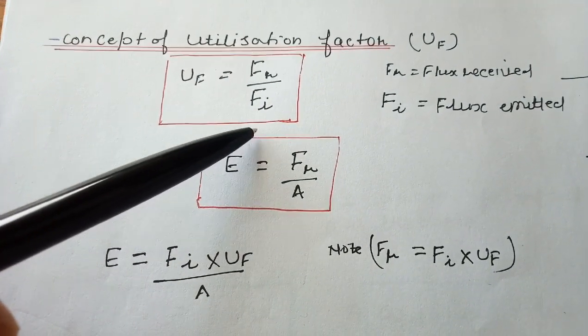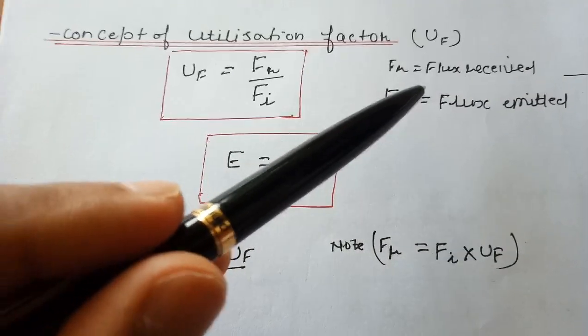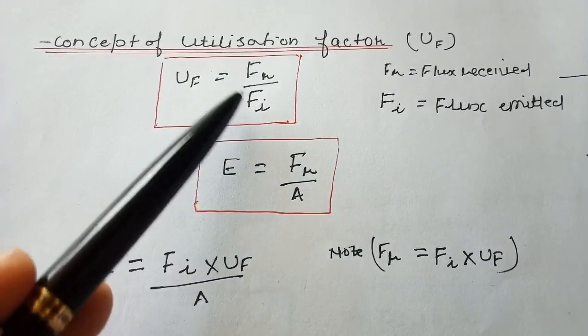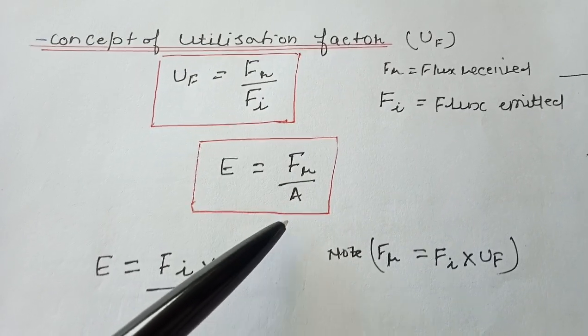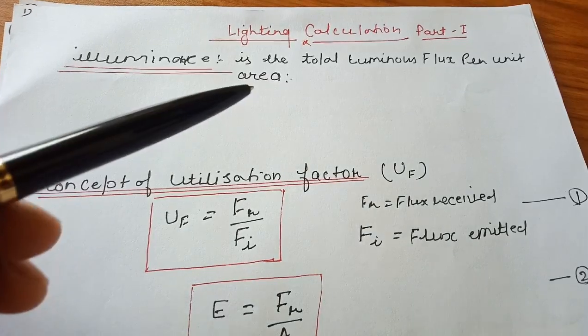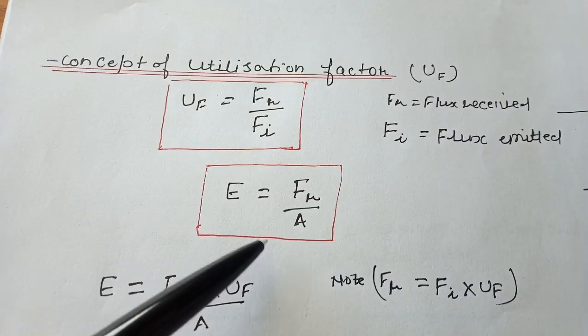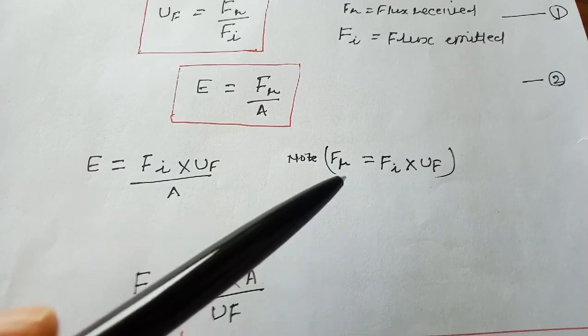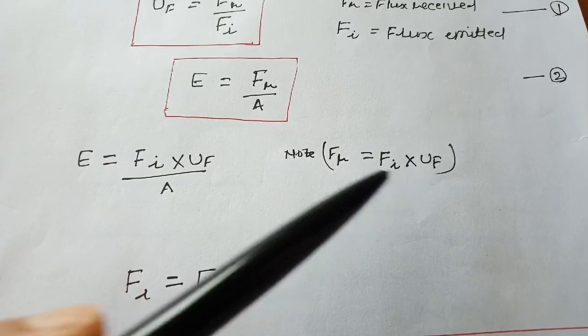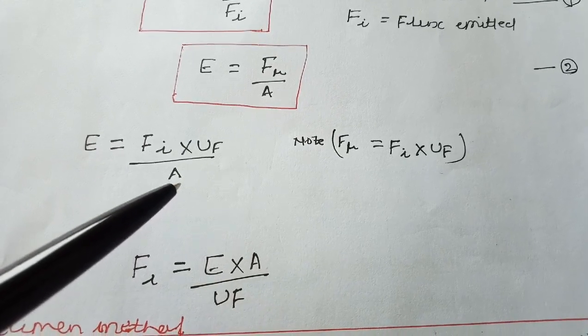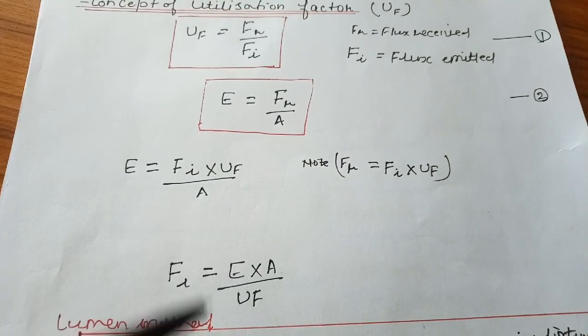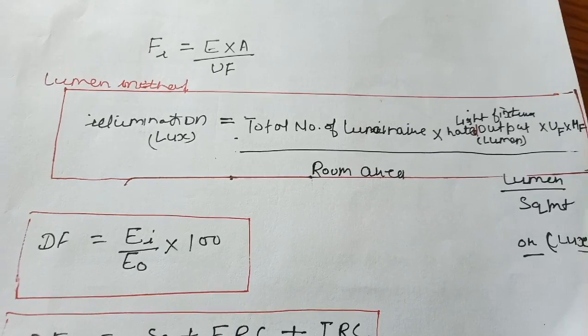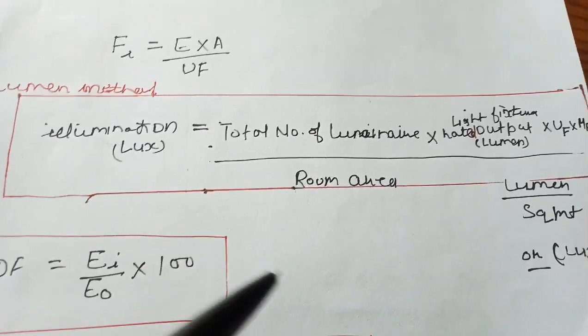Here, Fr is flux received and Fi is flux emitted. Illumination E is equal to flux received divided by area — the total luminous flux per unit area. Rearranging the formula, Fr equals Fi into UF (utilization factor), so E becomes Fi multiplied by UF divided by area. This gives us another formula for illumination. Next, we discuss the lumen method, used to calculate the number of luminaries, number of lamps, and number of fixtures.